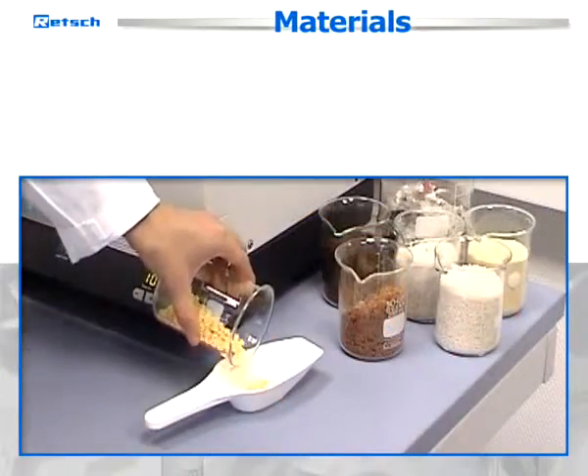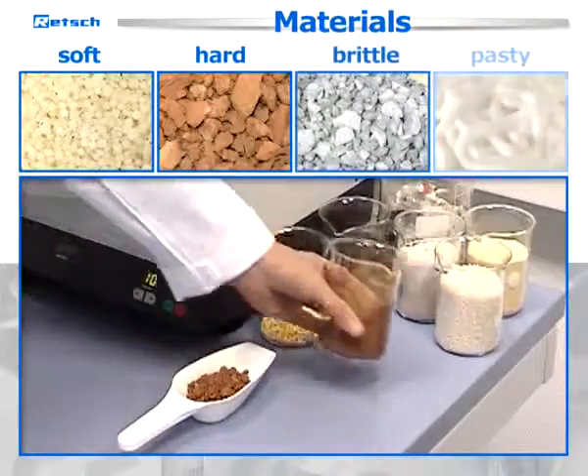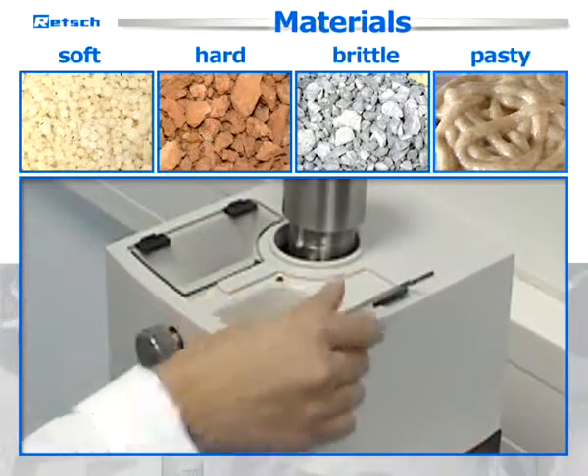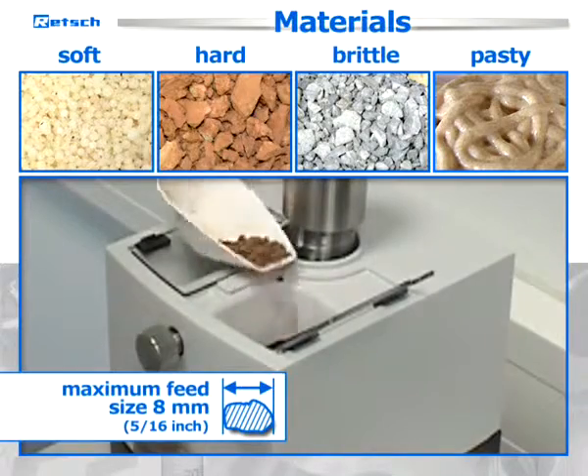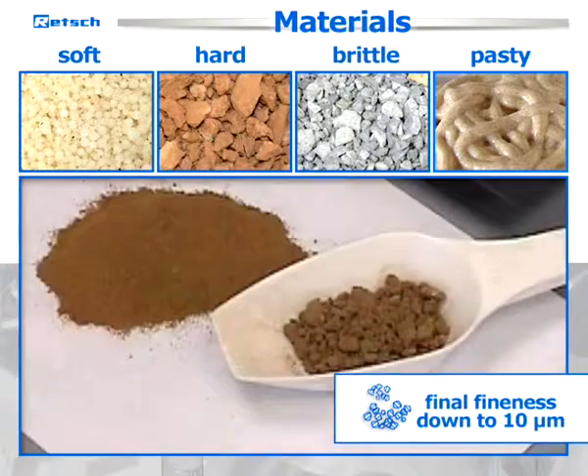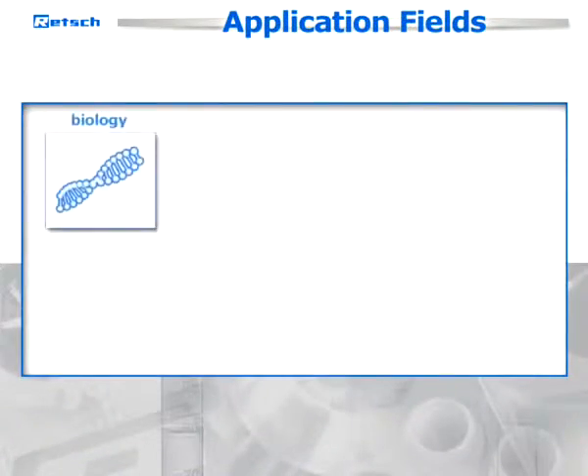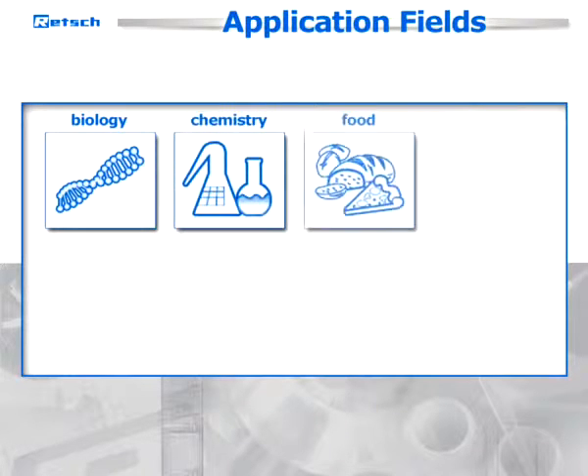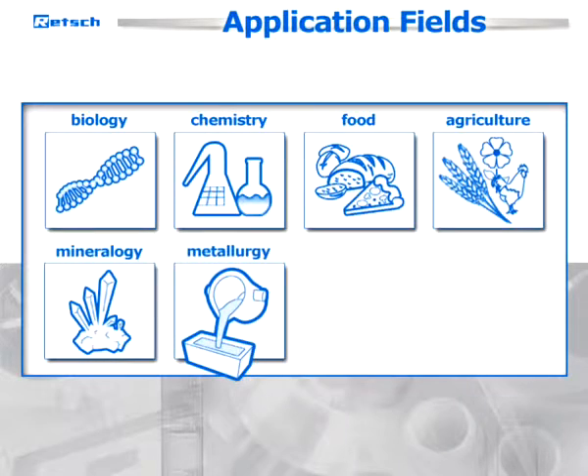Retsch mortar grinders are suitable for processing soft, hard, brittle, and pasty materials, with a maximum feed size of up to 8 millimeters. Due to an achievable final fineness of down to about 10 micrometers, the RM200 covers a wide range of applications from fields such as biology, chemistry, food, agriculture, mineralogy, metallurgy, environment, and pharmaceuticals.